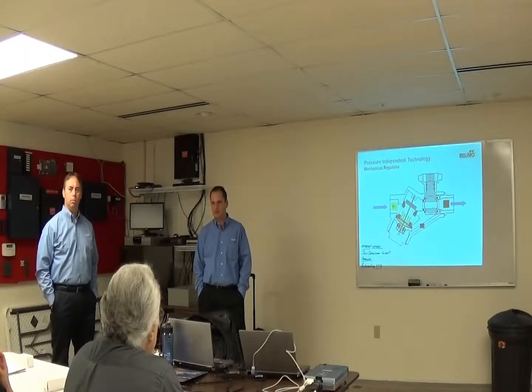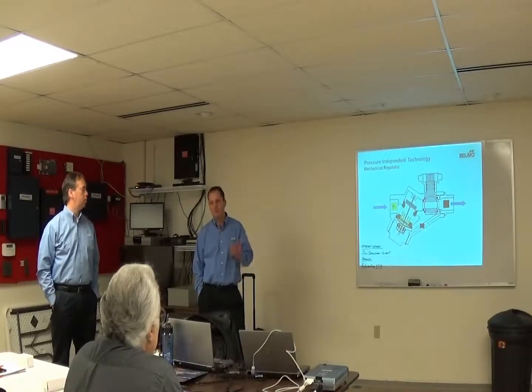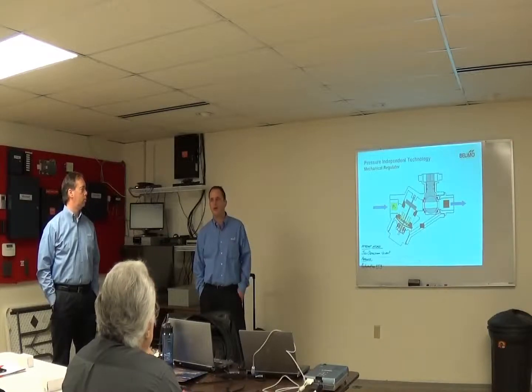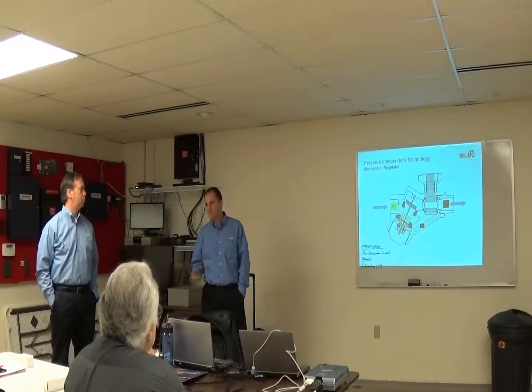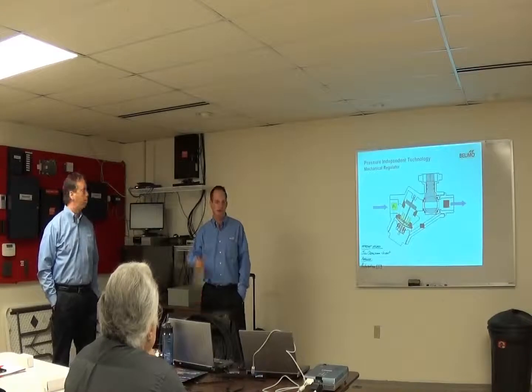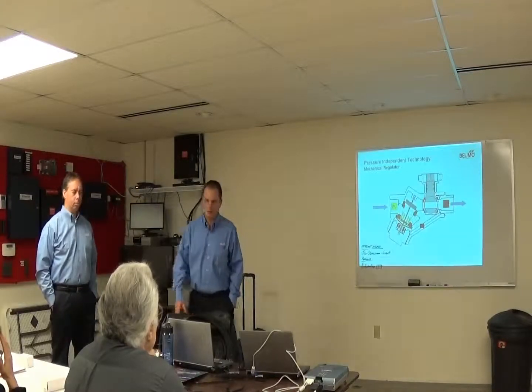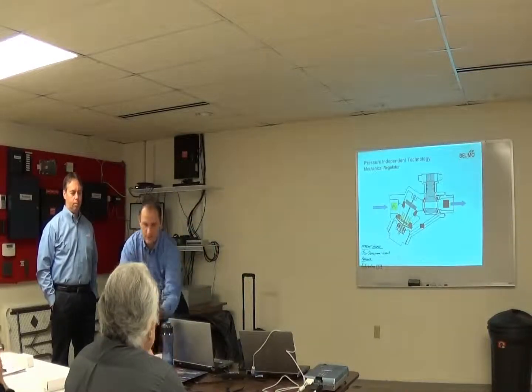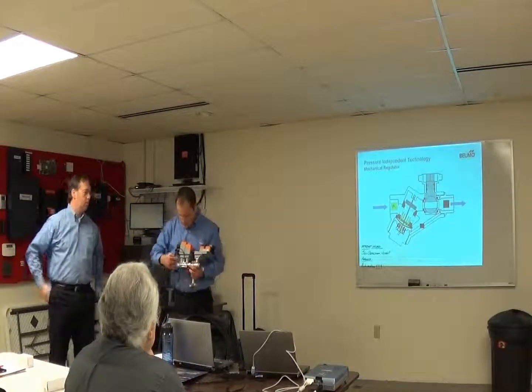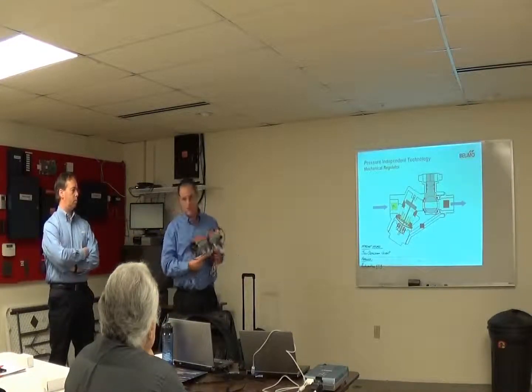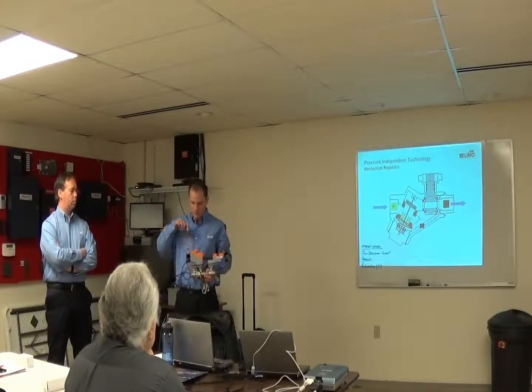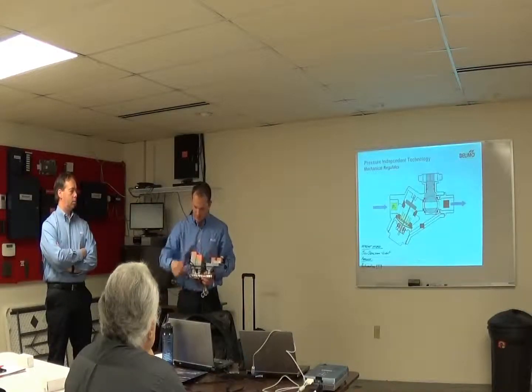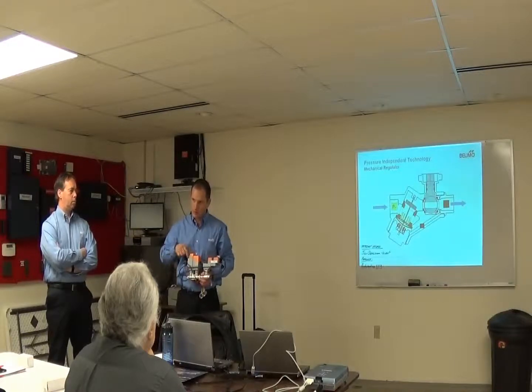All fluid is at a specific gravity, a certain viscosity. Water, once we introduce propylene or ethylene glycol or whatever, it's going to change that. And the way these things work, basically, there's a signal that goes this way. If you look inside this thing, there are two posts in there. They're chamfered off, so this one is chamfered off this way and this one's this way. They act as mirrors, so it's sending a signal this way, and then this transmitter is sending a signal this way. The time it takes from here over to here tells us how much flow.